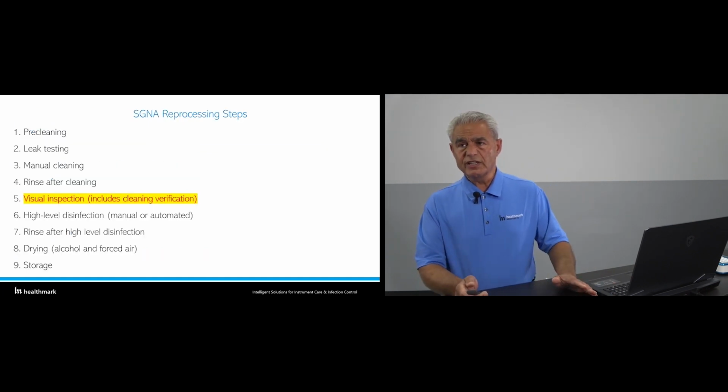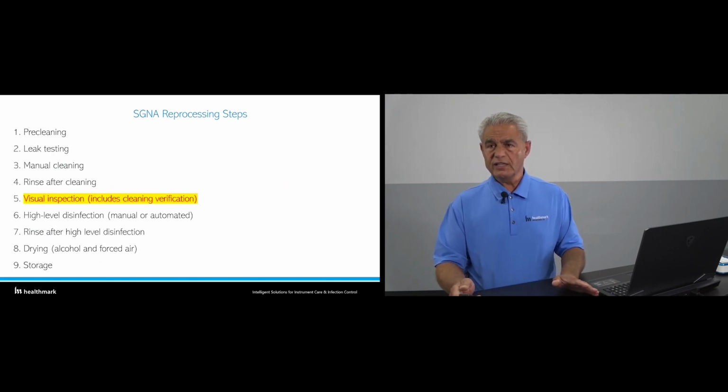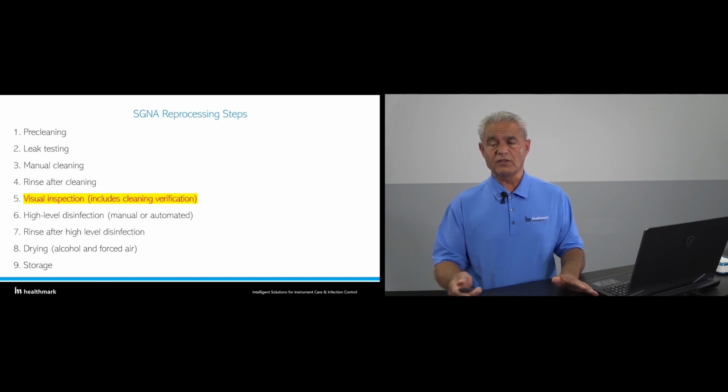Again, SGNA guidance talks about the 9 steps of cleaning: pre-cleaning, leak testing, manual cleaning, rinse after cleaning, and visual inspection, which includes cleaning verification as part of that. Then after you process it with high-level disinfection, either manual or automated, rinsing after that, and drying and storage.